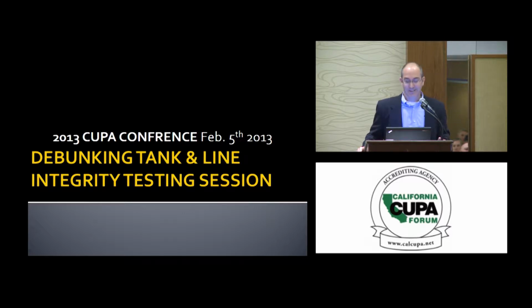But the NFPA came up with some, wouldn't really call them standards, but they referenced something called a standpipe test as early as 1964. That's the earliest I could find anyway. And they realized that it was not a very valid precision test. It had a lot of shortcomings. It was somewhat dangerous. There's product up above grade. There were no real standards. They weren't able to account for the thermal expansion and contraction of the product and for the end deflection that occurred. Moving into the 70s, there were some methods that started to account for some of those things.